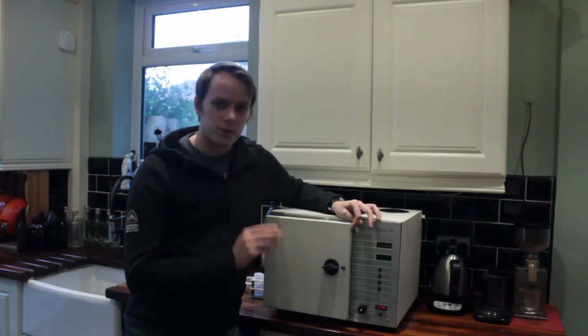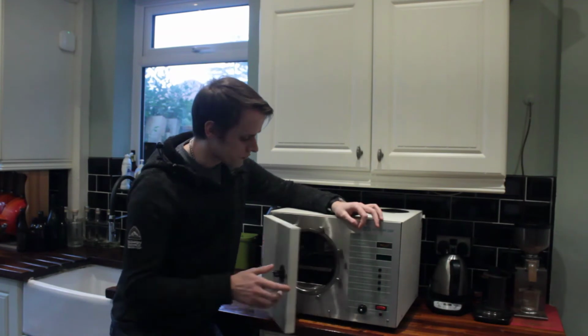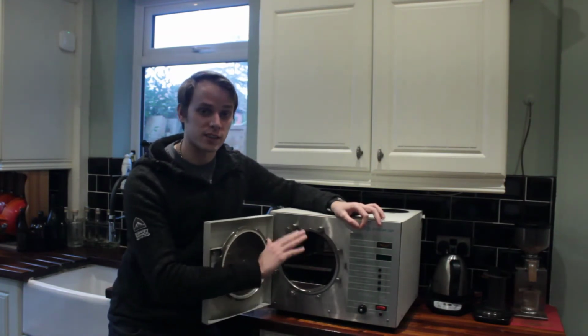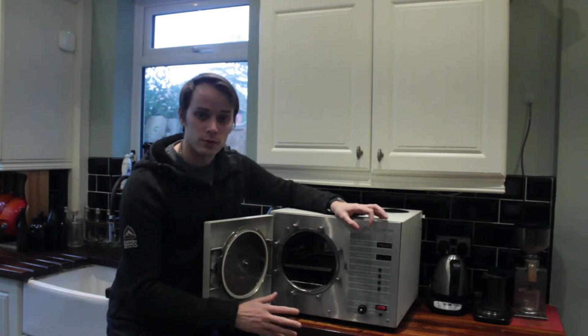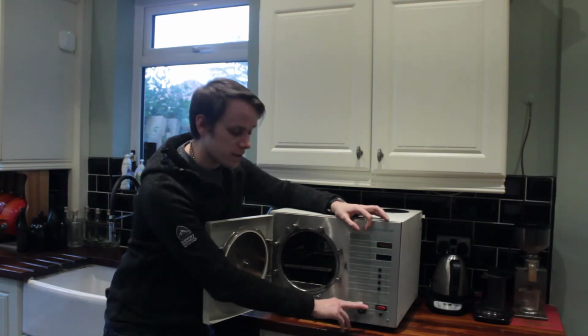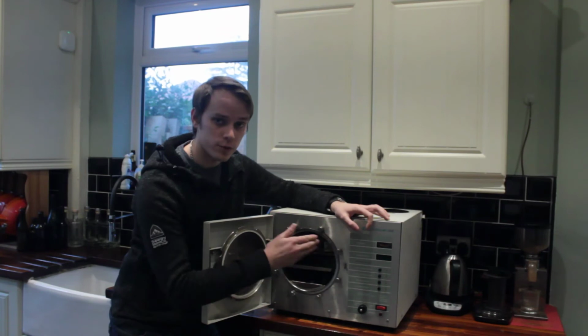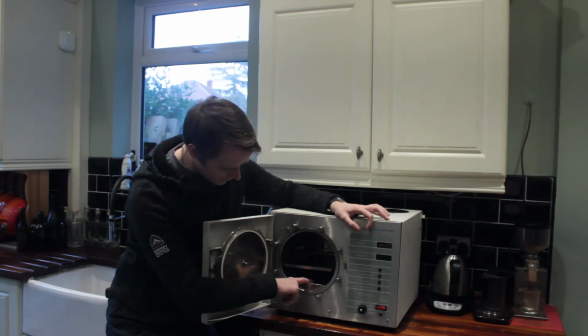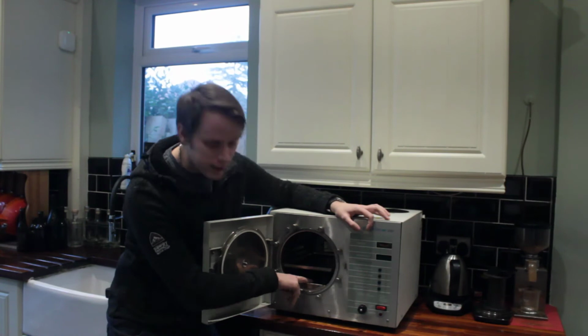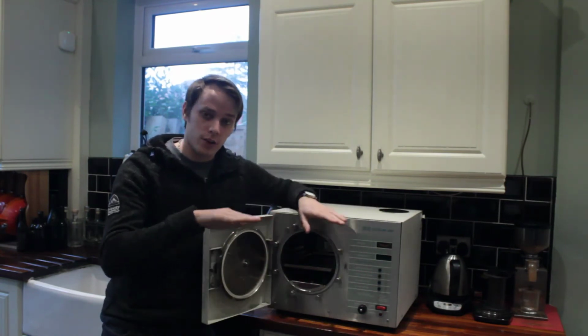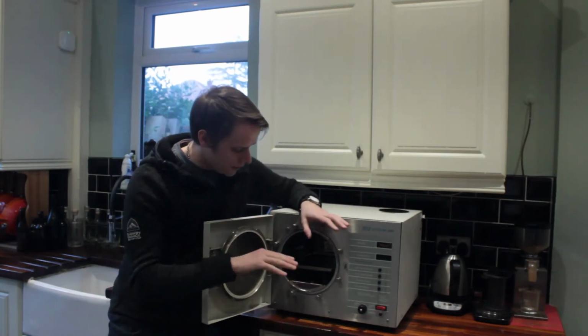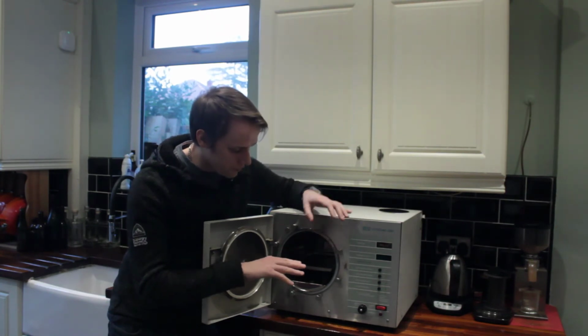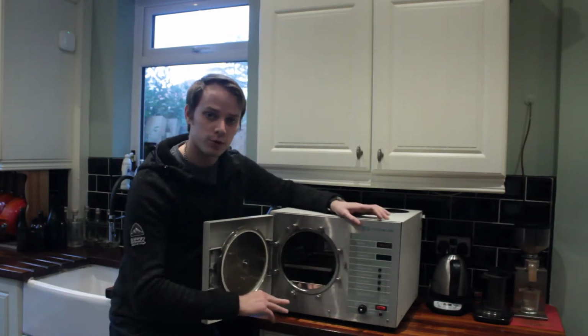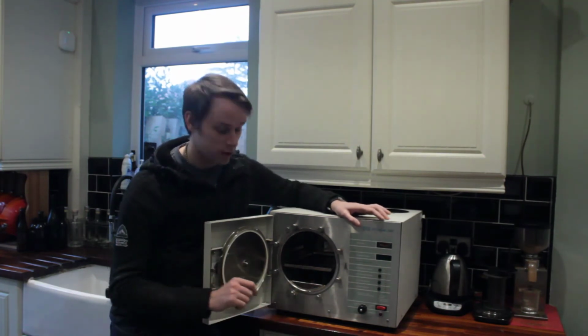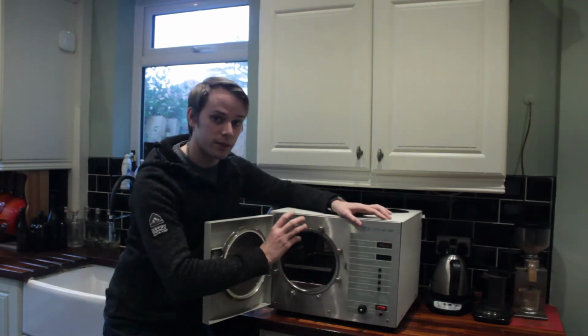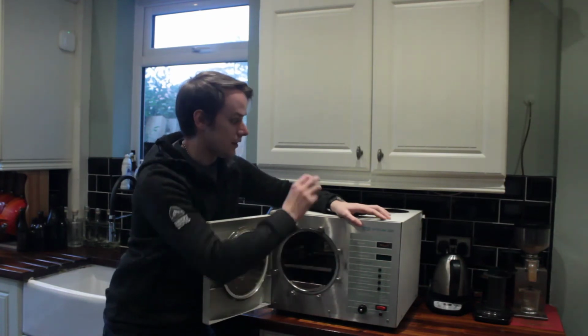First off, we want to fill our vessel, so we want to add some water into here that we can convert into steam. On this model we have to do that manually. On the side here we have a valve for allowing water into the vessel, and inside we have a little hole in the mesh that covers the heating element, and what we want to do is open this valve and allow enough water in that it reaches that little hole, and then we can shut that valve off and isolate the pressure vessel here from the reservoir.